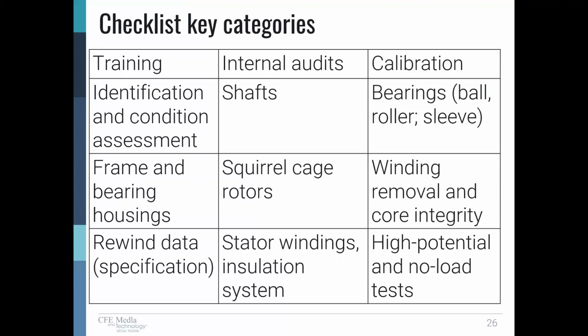Condition assessment: what's wrong with the motor, identify what happened. Shafts, bearings, and housings: we want to make sure that the shafts are straight, that the shaft bearing fits the journal, fit on the shaft, and the housing is good. The winding: a lot of attention to winding details, how the windings are removed, stator windings, what goes into the windings, and verifying the data, again, going back to that specification. And then electrical testing, high potential tests, no load tests of the completed machine.